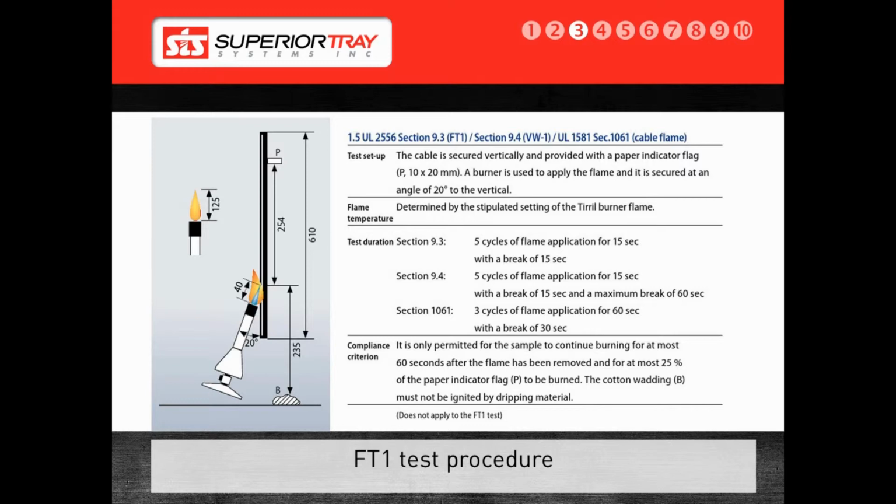This, of course, is all taken into account when we develop a cable bus for a customer. We specify conductors and all materials with these factors in mind. Every component inside our cable bus has been flame tested to make sure that in the event of a fire, a SuperiorBus will not allow the fire to propagate through the cable bus.